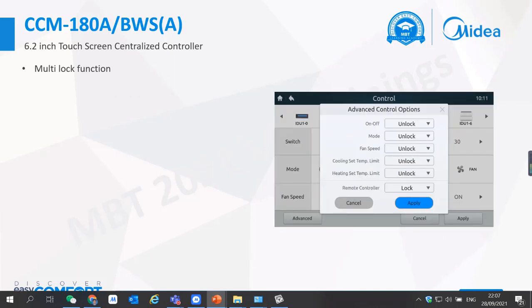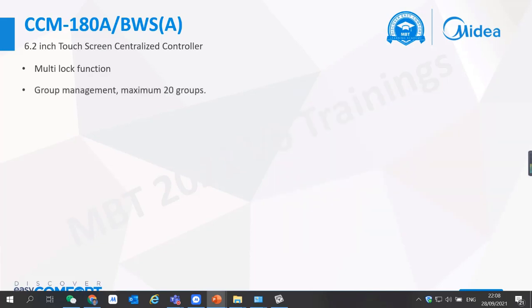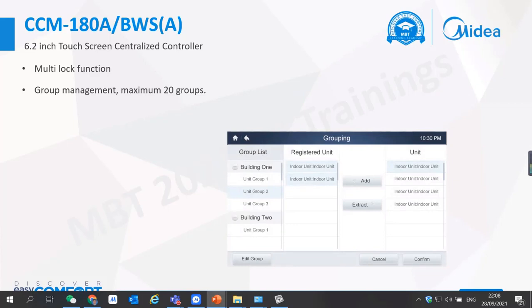So the basic control we already discussed, that it can set the mode, temperature, etc. Apart from that, advanced control. What is advanced control? You can set the cooling set temperature limit. Cooling temperature limit means the minimum cooling temperature. Usually the range is 17 to 30, but you can lock the range to 20 to 30, so the cooling point cannot go below 20, so it can help you save energy. Similarly, in the heating mode, you can set the upper limit for the heating mode. Basic is 17 to 30, but you lock it to 25, so the customer cannot take it above 25, he will save some energy. And you can lock the wireless controller from this. You cannot lock the wired controller from this. Group management, 64 indoor units, you can divide them into different groups for easily controlling them.